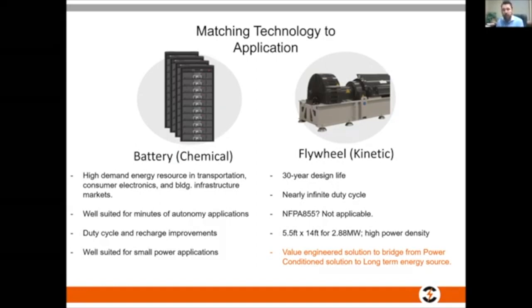Moving forward, I'm going to show you a couple of one-lines, but really the one difference you might argue is how do we store energy? How do we go from a point where the input breaker has opened because we have a problem - a mains detection relay that said 0 volts, or the supply is just bad, whatever that might be: poor power quality, high harmonics, spikes from lightning strikes, whatever it is - over to a diesel generator.